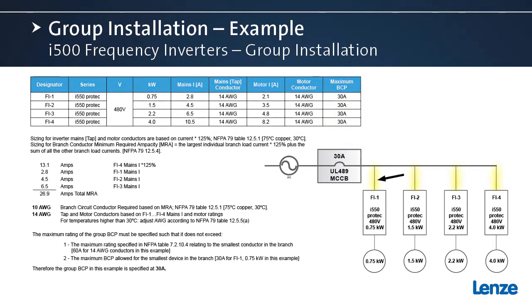These are the conductors that connect from the branch conductor to the frequency inverter itself. These are connected directly to the input terminals of the frequency inverter. Those are sized based on NFPA 79 table 12.5.1 using the mains current ratings of the inverters. Next, we'll have to size the branch circuit conductor. That's the larger conductor that feeds all 4 frequency inverters.